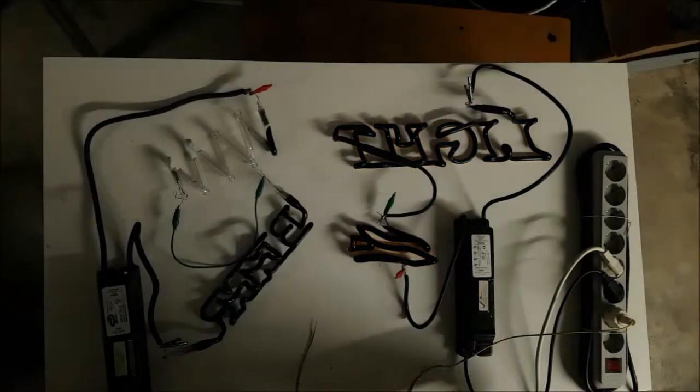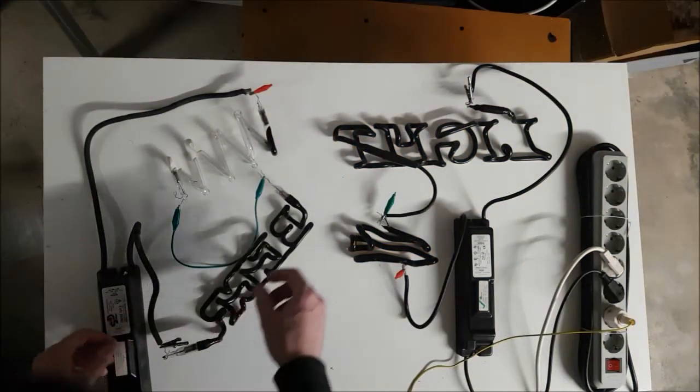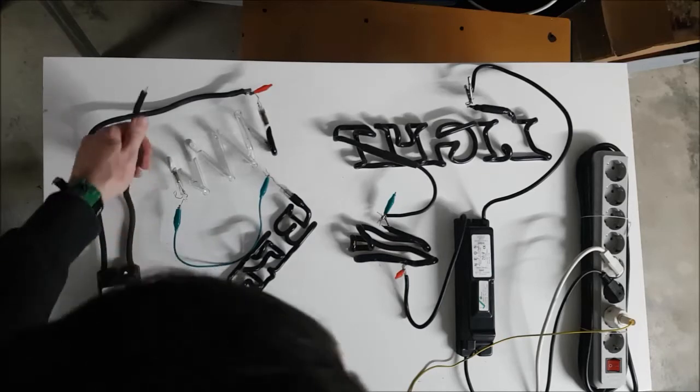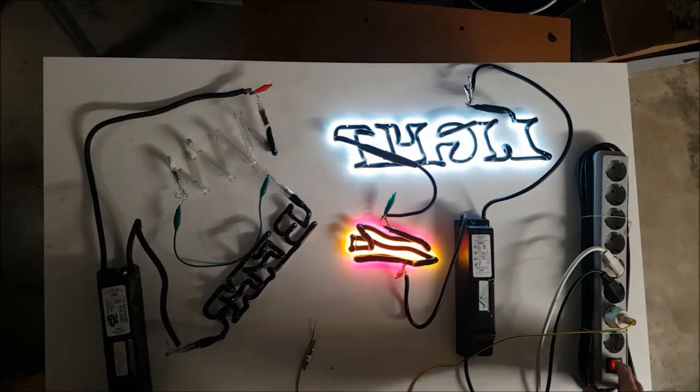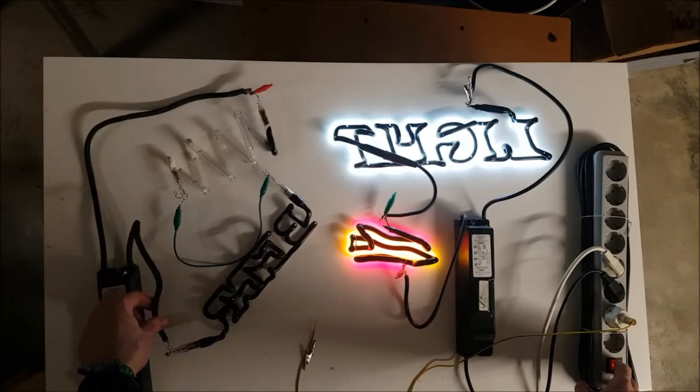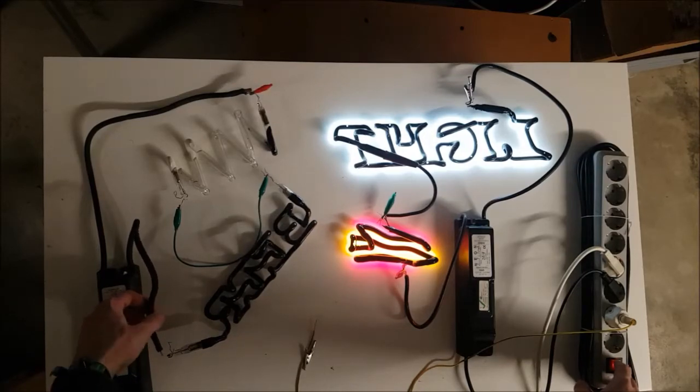So I'm turning off the power and I'm loosening this connection here. Just bending this up a bit. Turn it on. That was the correct behavior. You see that it flashed, detected the open circuit and shut off. So even when I connect the wires now, there is no light.